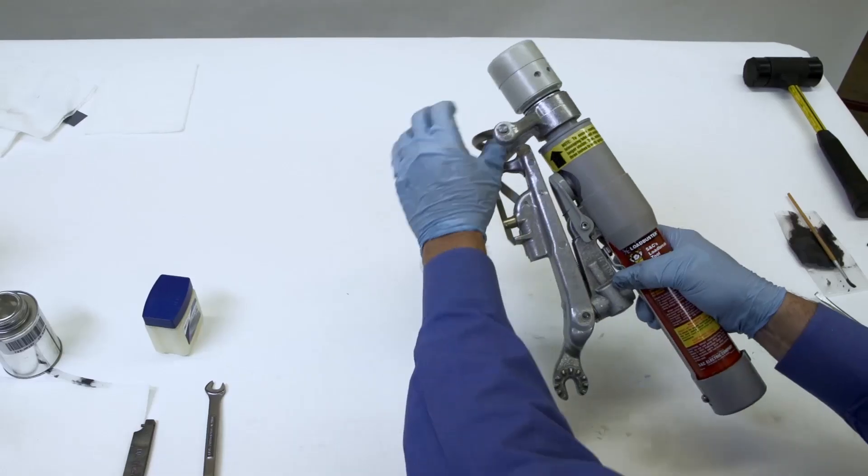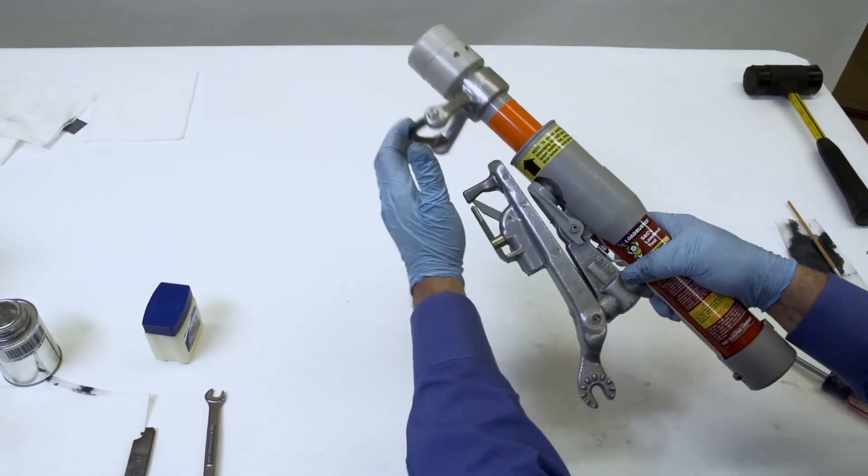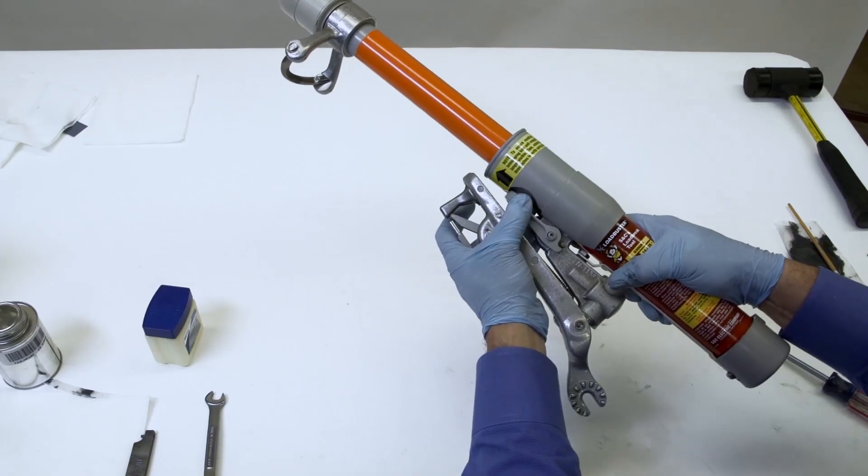It's important to operate the tool several times to make sure that the trigger and resetting latch perform properly. Optionally, with a force gauge, check that the trip force is between 20 and 27 pounds for Loadbuster model 5300R3 and 20 to 29 pounds for model 5400R3.